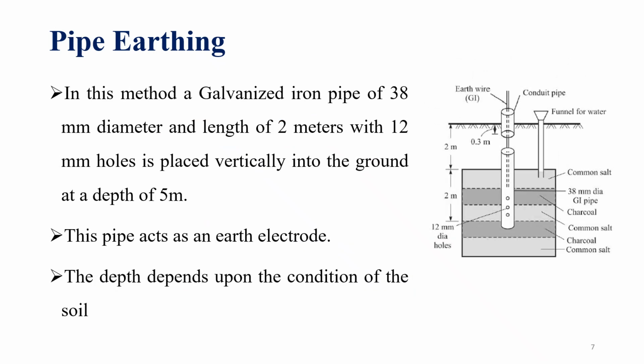Next, the second type is pipe earthing. In this method, instead of a plate, as we have discussed in the previous type, we are going to use a GI pipe of 38 diameter. This is the GI pipe. This GI pipe we are going to use for earthing, and it will have a length of around 2 meters, with 12 holes. On this pipe we are going to have holes with a diameter of 12, and it is placed vertically into the ground at a depth of 5 meters. Okay.